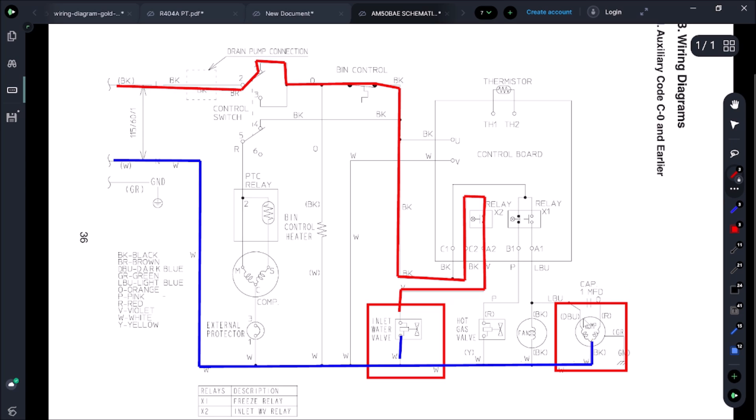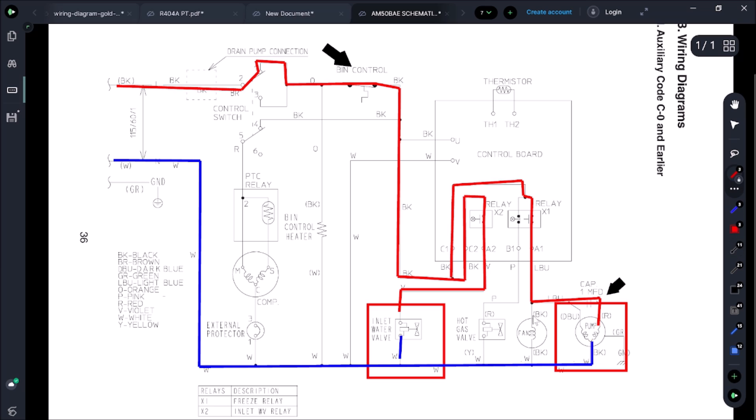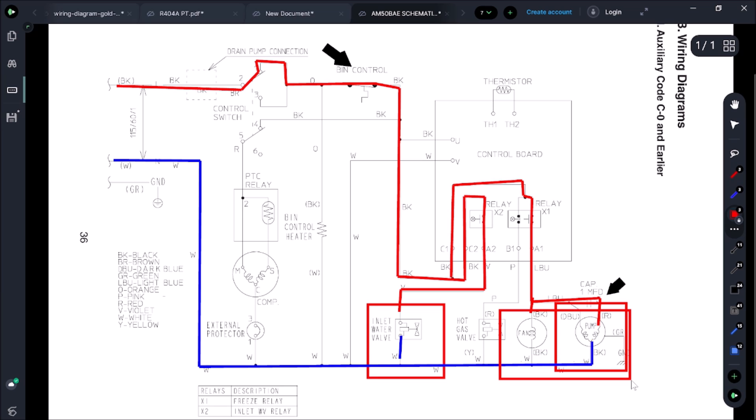Let's do our pump really quickly. We come through here. We have a cap. But we are coming through this relay right here. Normally open normally closed. And we're back feeding to the same spot. Same thing here. If our bin control is open, this is obviously not going to run. And you can actually see the condenser fan is wired with it together. So in theory they should always be running together, the condenser fan and the pump. So that's a good hint. If the pump's running and the condenser fan's not running or vice versa, that's something we need to look into. These little subtle hints that the schematic gives us are super important. That's why it's important to take five minutes to read the schematic. It'll teach you the sequence of operations.